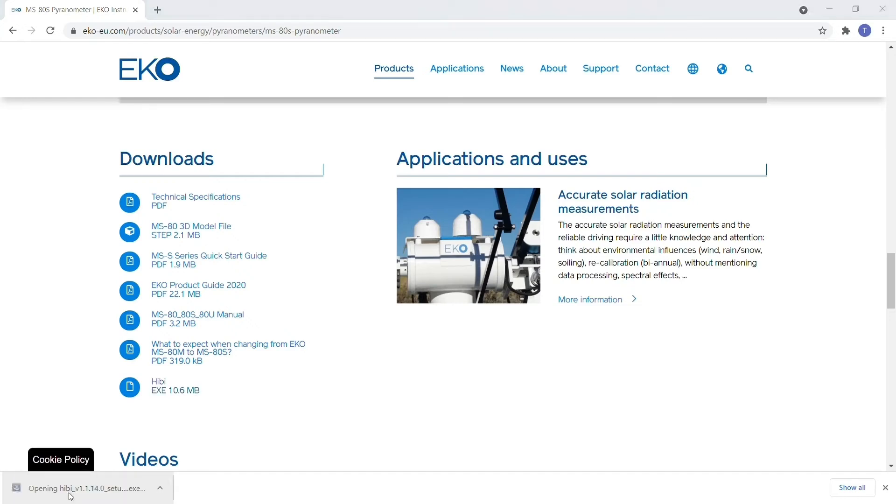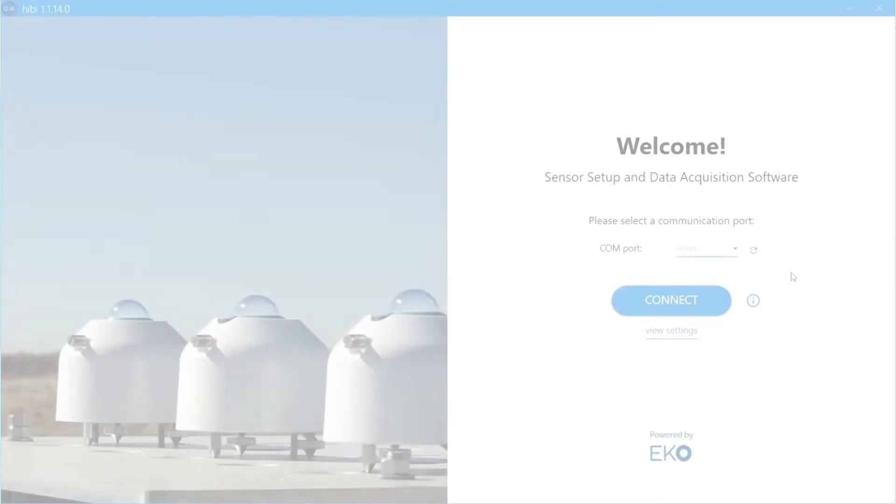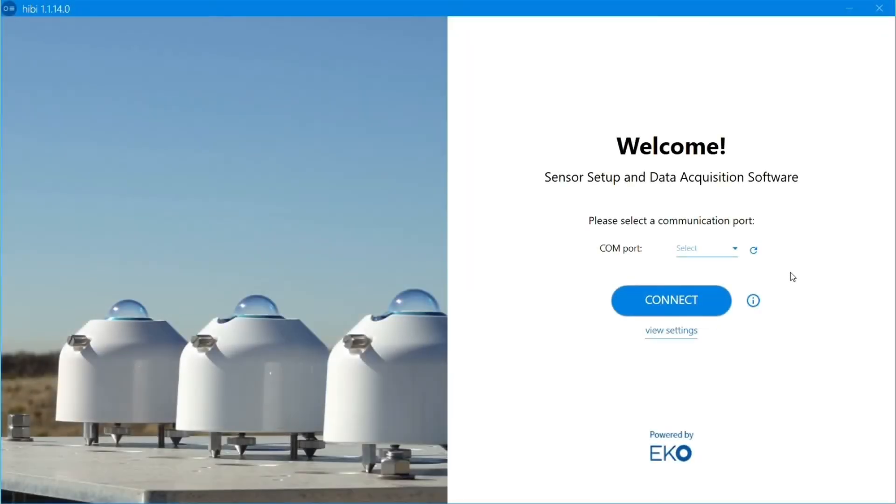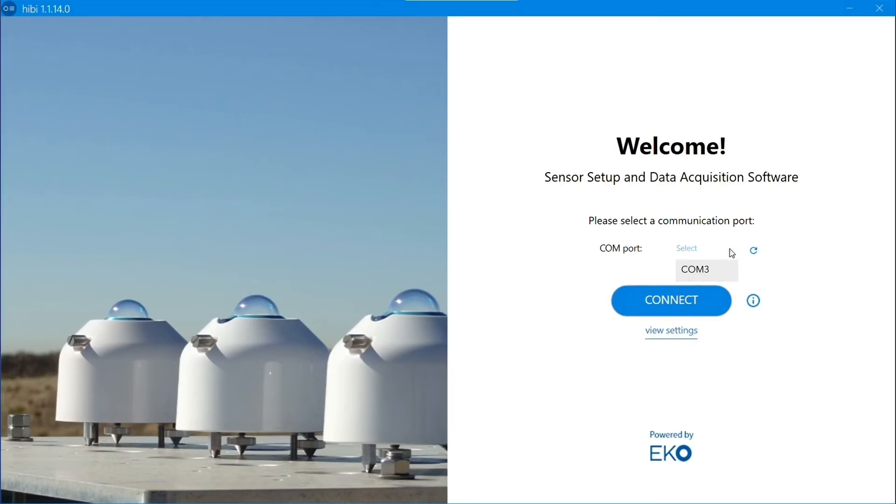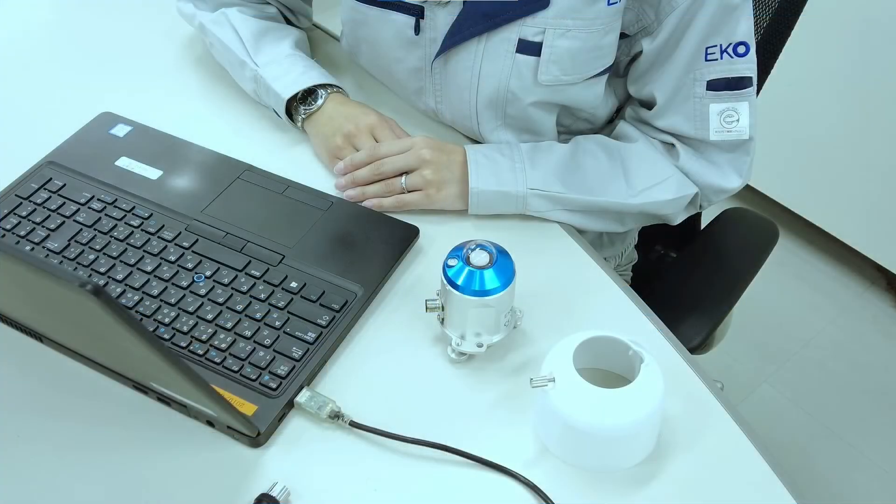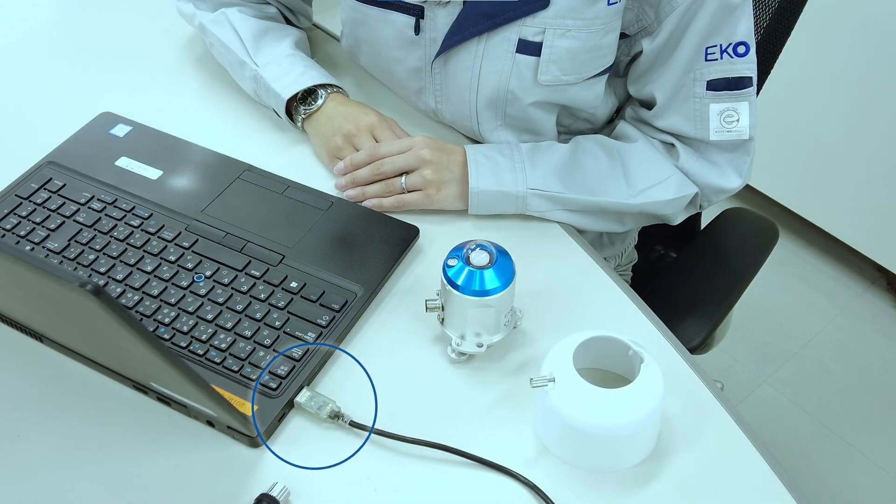Once you've installed and launched hibi, you'll be greeted to the welcome screen, where you'll have to select the USB COM port that your S-Series Pyranometer is plugged into from the drop-down menu. The COM port will be pre-populated based on where you connected the RS-485 USB conversion cable to your PC.